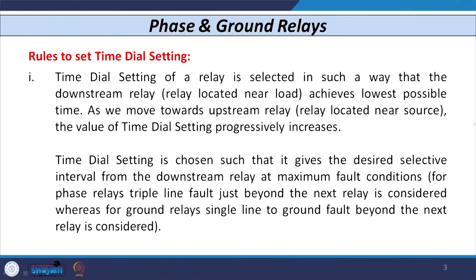Similarly, let us discuss the rules to decide the time dial setting of phase and ground relays. The time dial setting is selected such that whichever relay is located near the load achieves the lowest possible time, and as we move from a downstream relay to an upstream relay, the time dial setting value increases. The time dial setting is chosen to give the desired selective time interval between downstream relays for maximum fault conditions.